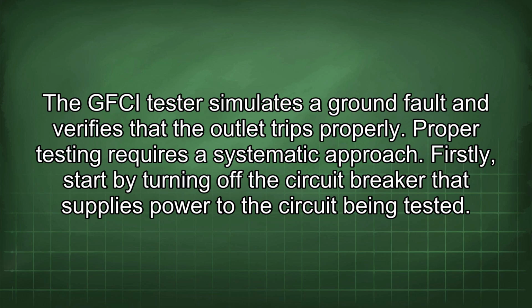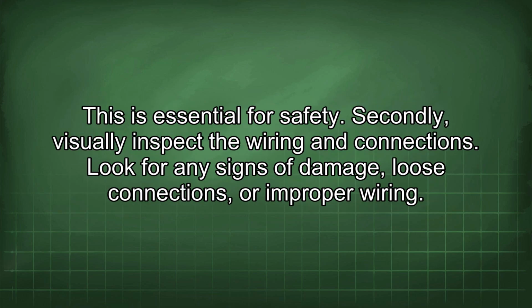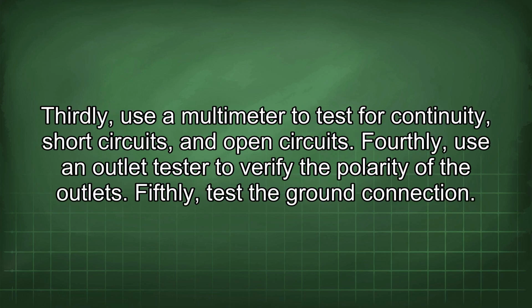Firstly, start by turning off the circuit breaker that supplies power to the circuit being tested. This is essential for safety. Secondly, visually inspect the wiring and connections. Look for any signs of damage, loose connections, or improper wiring. Thirdly, use a multimeter to test for continuity, short circuits, and open circuits. Fourthly, use an outlet tester to verify the polarity of the outlets. Fifthly, test the ground connection.